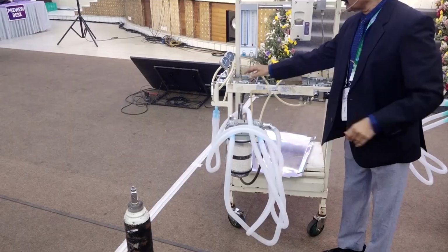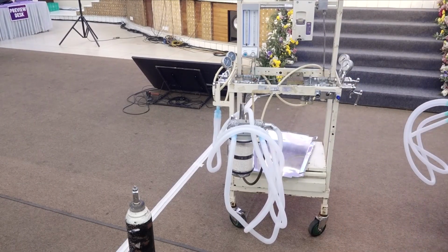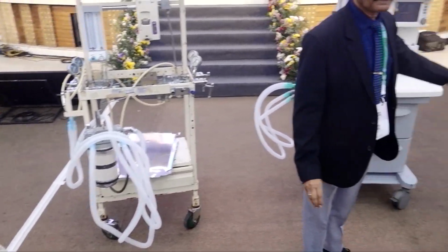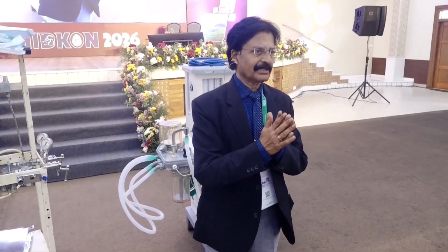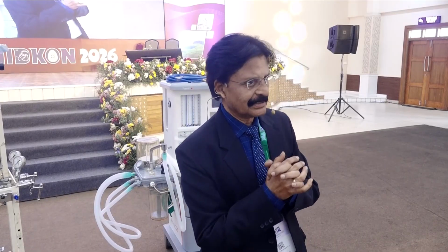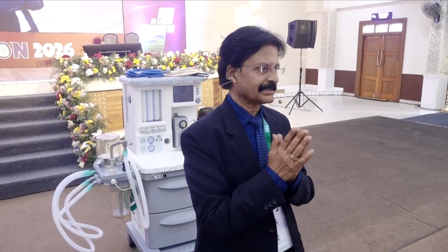Now coming to the pressure regulators. I told you about the pressure regulators. Even in these workstations, you have the pressure regulators to reduce the cylinder pressure to 45 psig, like the older ones. So why does the pressure of the cylinders have to be reduced? Straight away, when we ask you in the exam, you will say that it is to prevent barotrauma. That is not the most important indication.